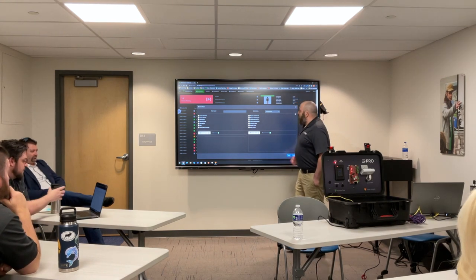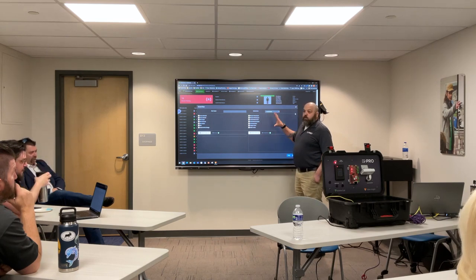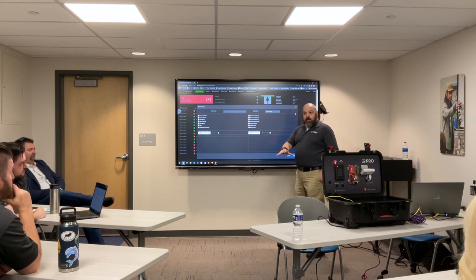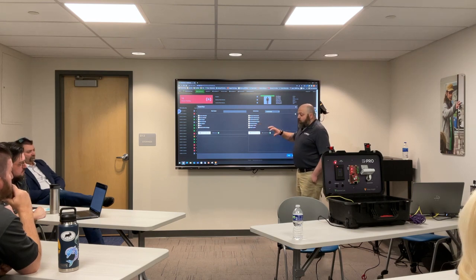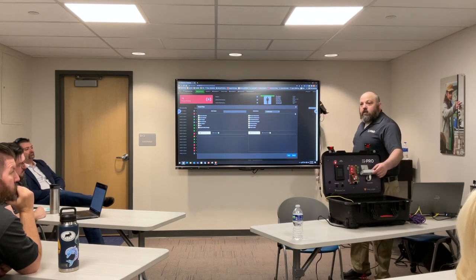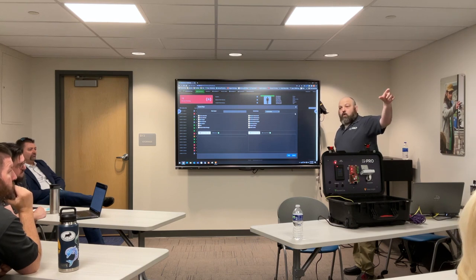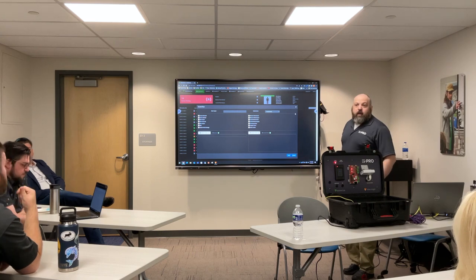In the way that I found, if you use one specific solution, there's only one specific way to defeat it. So if you guys have ways that you've identified that work, we can figure out how to get those in here to work also. Or if you want to bracket it and use a camera, some of our cameras that have AI built into them, we have an extension software set where you could point it at the door, box off the top part of the door, and then it can detect if the door is open or closed. And then you can say if the door is open for greater than a minute, go ahead and generate an alarm. So we could look at doing something like that.